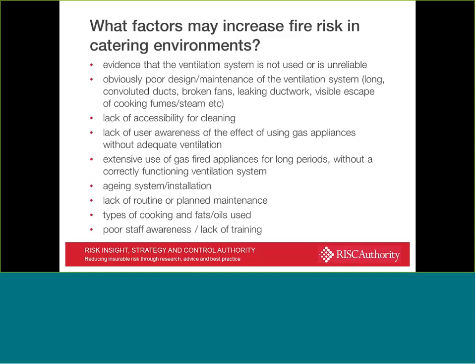Deep fat frying produces a particular type of almost see-through brown grease deposit. And frozen foods, particularly if they've got large quantities of water in them and they're very well hydrated, will create a very different type of grease, which has a shiny, hard look to it. So there are a number of issues which we do need to consider in that respect, and I think there are other factors associated with the types of oils used and the frequency of them being changed.